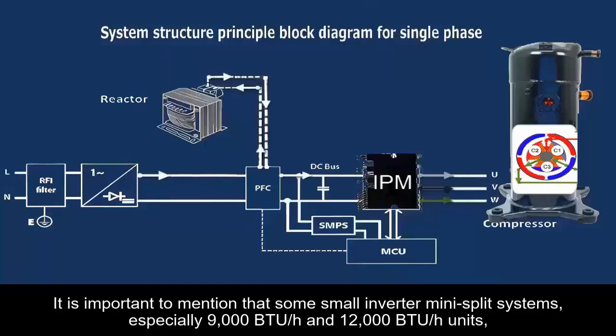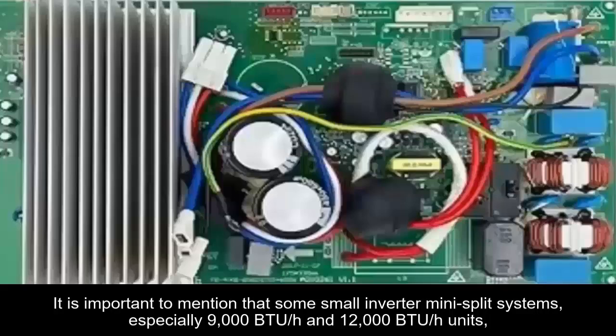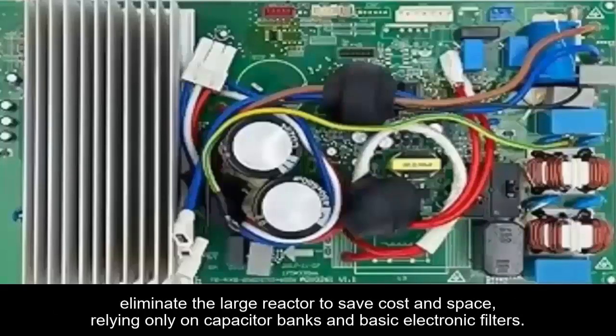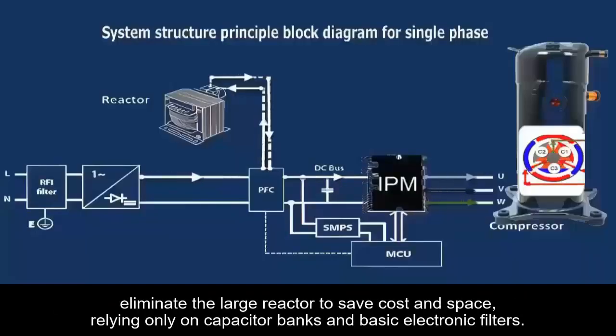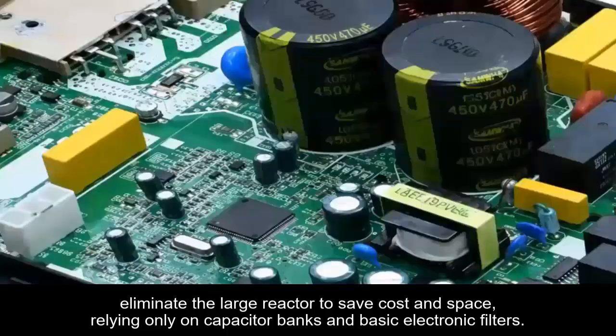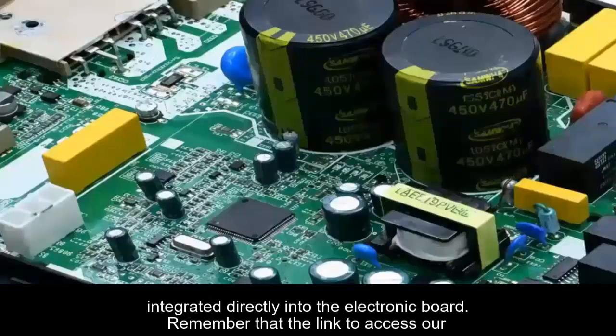It is important to mention that some small inverter mini-split systems, especially 9,000 BTU per hour and 12,000 BTU per hour units, eliminate the large reactor to save cost and space, relying only on capacitor banks and basic electronic filters integrated directly into the electronic board.